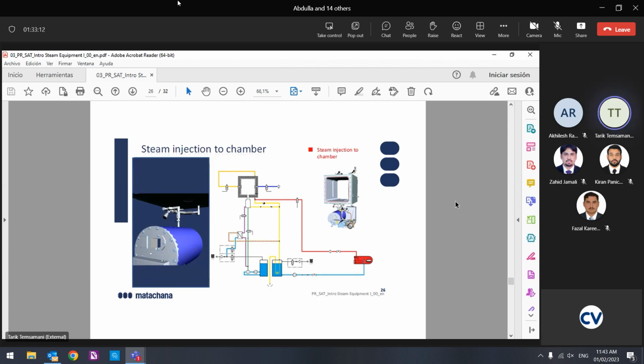Into the chamber, to the jacket, not to the chamber. This is an error here. Steam to the jacket. This valve is an MV5, the most used valve in the machine. It's always on and off because we put steam here, we lose the pressure, we open it again and again and again. It works a lot. Okay, it's a pneumatic valve. You know this pneumatic valve is working a lot.